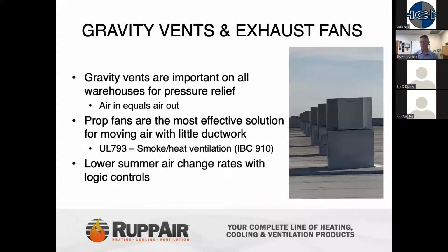So if you're utilizing the direct fired systems, either 100% or recirculating style, basically air in, which is called out by code, needs to have air out. Again, these buildings have gotten so tight that just having doors alone in the space with cracks around them is not enough normally to relieve these buildings. So gravity vents are a critical part of the design to make sure you meet those ventilation requirements that ASHRAE is calling out for. I've been in buildings where they don't have gravity vents and they start to have moisture issues, and just cracking some dock doors makes the moisture go away.